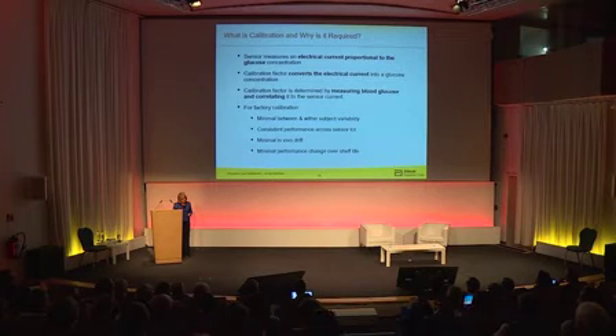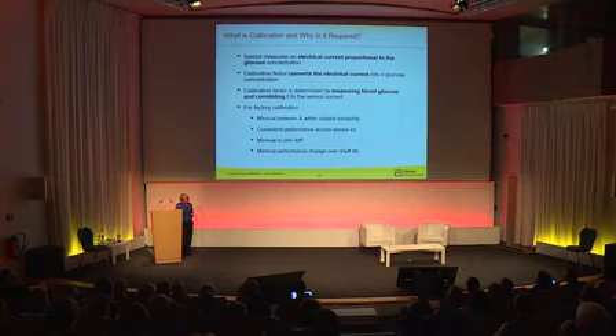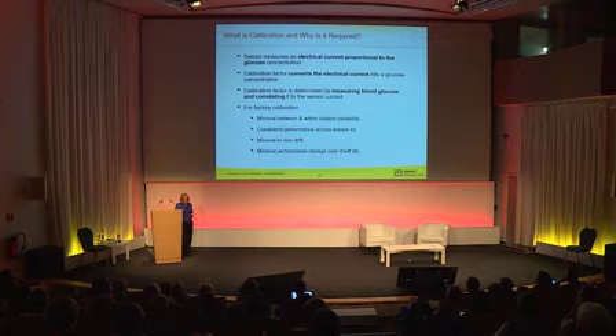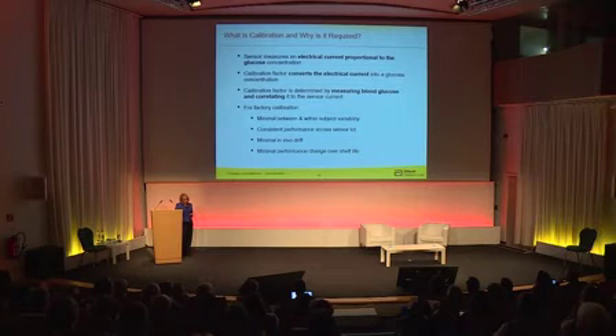What is calibration and why is it required? Often the sensitivity of sensors is not known, and it's not known if that sensitivity will be stable during use. A sensor measures an electrical current proportional to the glucose concentration. The calibration factor converts the electrical current into a glucose concentration. The calibration factor is determined by measuring blood glucose and correlating it to the sensor current.